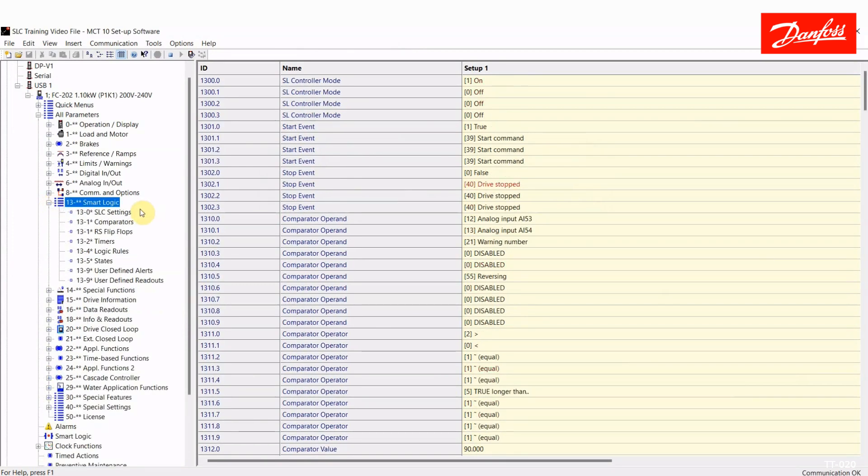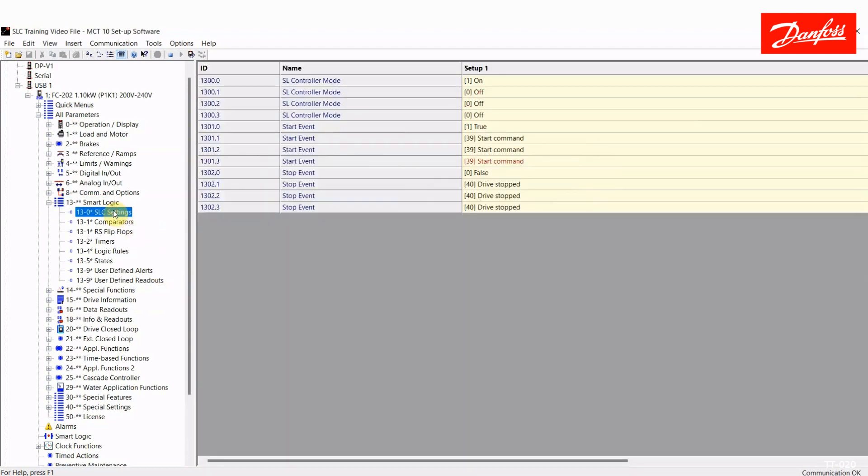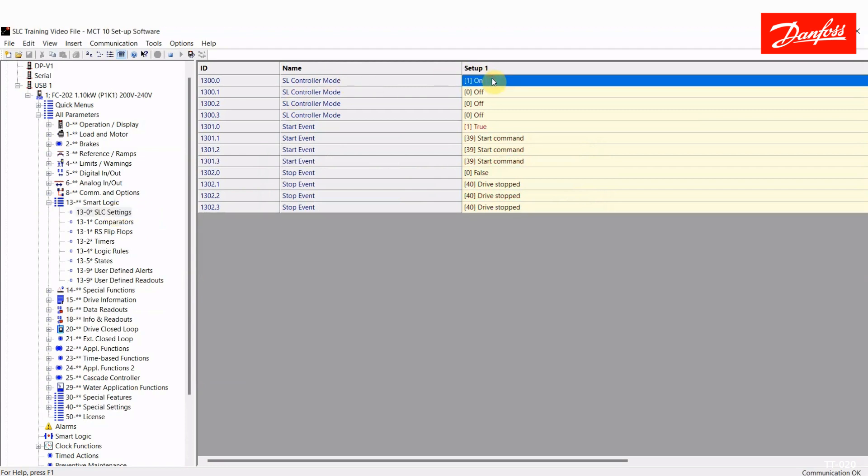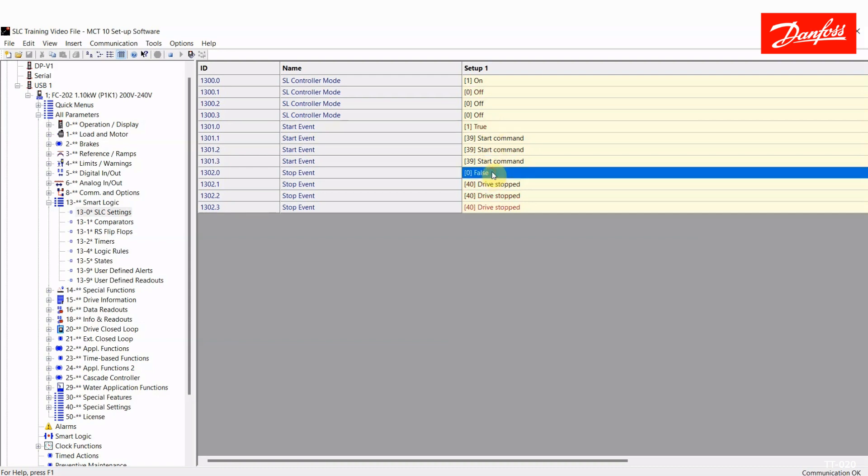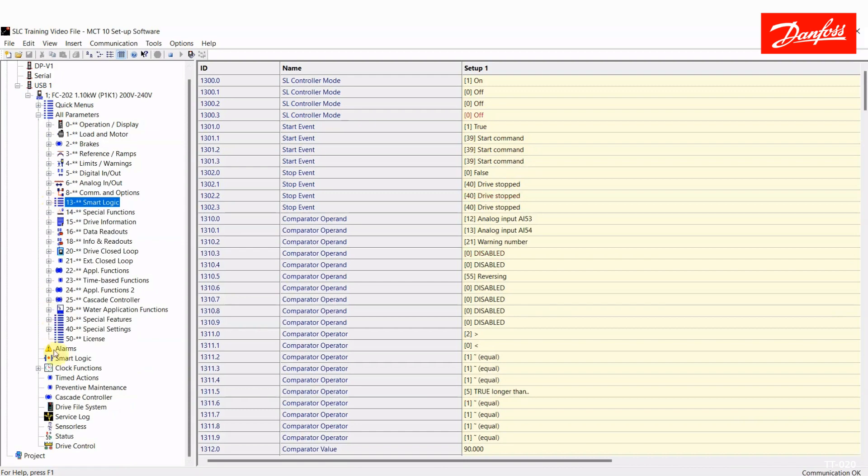Okay, so now that we've looked at the various functions that you can use in the smart logic controller, let's take a look at the plugin and the sequence that I've created. First of all, I'll show you that the smart logic settings for smart logic controller one that I'm using have to be turned to on. And the start event for this sequence will be true, meaning I am always in the smart logic controller sequence and the stop event is false. So the drive will always obey commands that are coming from the sequencer.